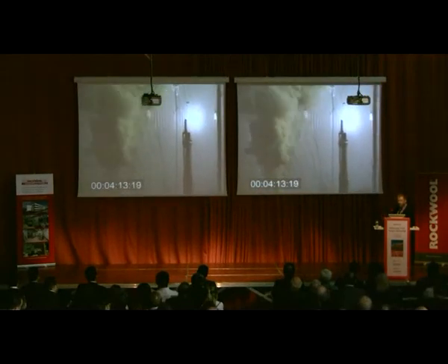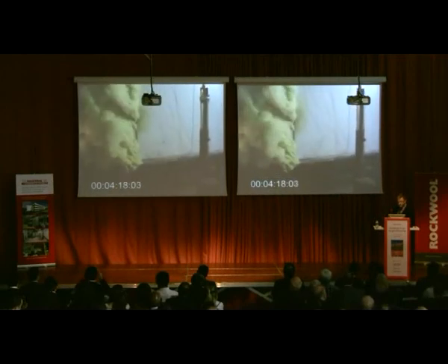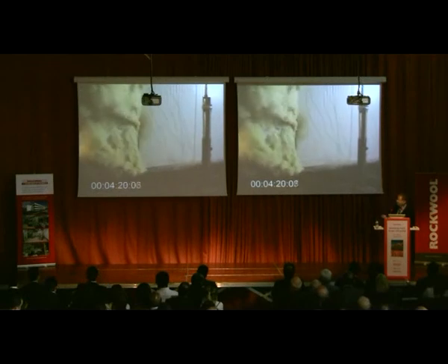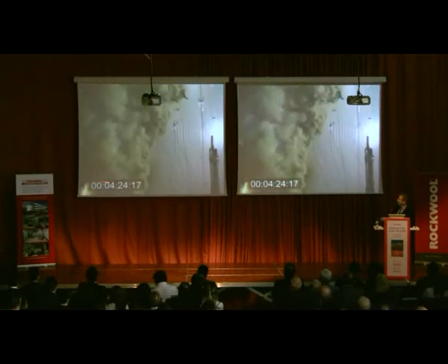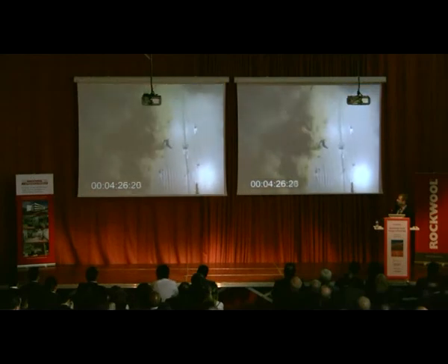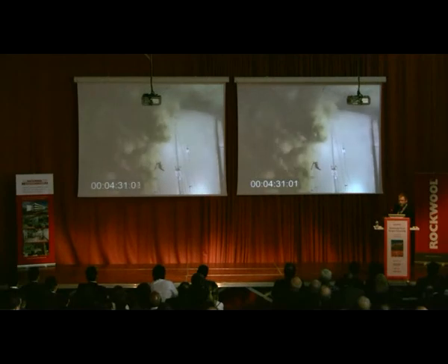It was between the frame and the panel. So this is what you may experience, or what may happen in a real fire just after 4 minutes. This construction was supposed to be classified for much longer fire resistance period.